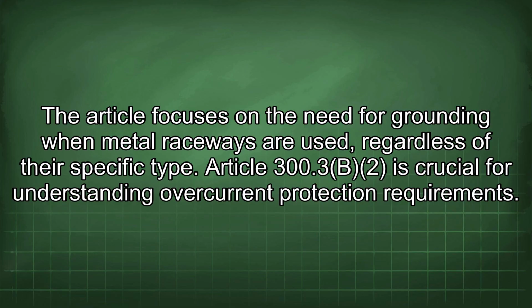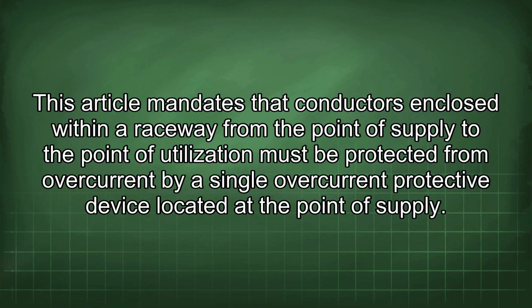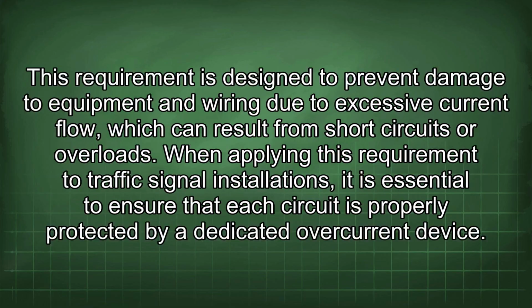Article 300.3(B)(2) is crucial for understanding overcurrent protection requirements. This article mandates that conductors enclosed within a raceway from the point of supply to the point of utilization must be protected from overcurrent by a single overcurrent protective device located at the point of supply. This requirement is designed to prevent damage to equipment and wiring due to excessive current flow, which can result from short circuits or overloads. When applying this requirement to traffic signal installations, it is essential to ensure that each circuit is properly protected by a dedicated overcurrent device.